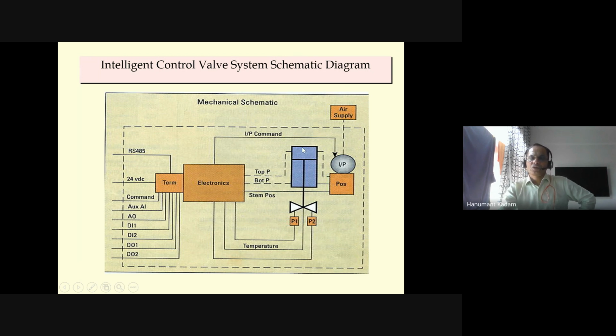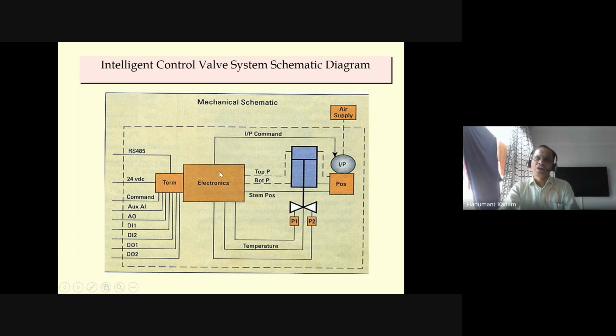So with these inputs, stem position, bottom pressure, top pressure, upstream pressure, downstream pressure, and temperature, the algorithm in the microprocessor is developed to get the diagnostics which we indicated earlier. And this electronics gives various digital outputs to indicate the health of this control valve. This microprocessor gives the command to the I2P, internally it is there. So this is what a valve positioner is.